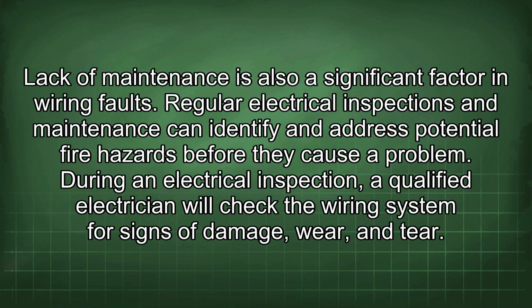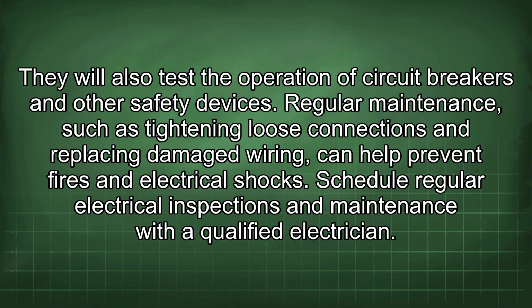Lack of maintenance is also a significant factor in wiring faults. Regular electrical inspections and maintenance can identify and address potential fire hazards before they cause a problem. During an electrical inspection, a qualified electrician will check the wiring system for signs of damage, wear, and tear. They will also test the operation of circuit breakers and other safety devices. Regular maintenance, such as tightening loose connections and replacing damaged wiring, can help prevent fires and electrical shocks. Schedule regular electrical inspections and maintenance with a qualified electrician.